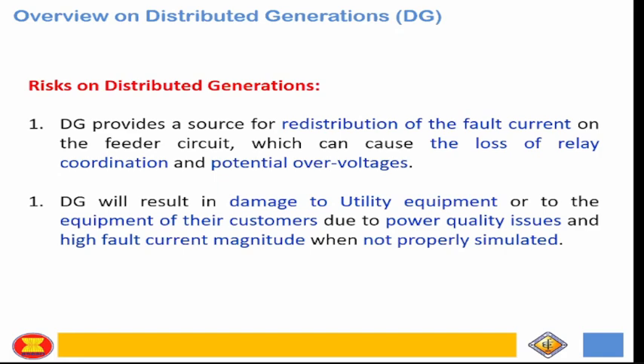And DG also can result in damage to utility equipment because, as mentioned, it's a fault contributor as well. If not properly simulated and it's found that the fault level will increase, and your protective device, like the fuse, has an interrupting capacity of 10 kA, and the distributed generation connected to that line raises the fault level, then during a line to ground fault or other fault scenario, the fuses may blow up. Although it can still protect, it may exceed the interrupting capacity of the protective device. So we need to review.